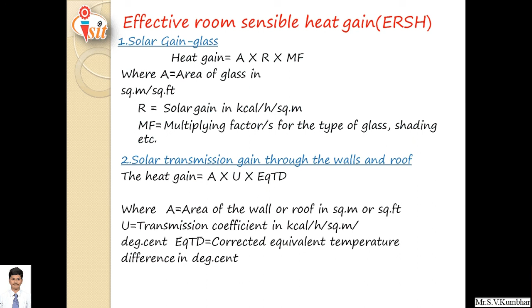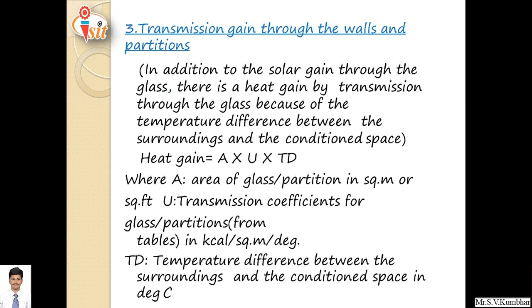Transmission gain through the wall and partition. Apart from solar gain through the glass, there is a heat gain by transmission through the glass because of the temperature difference between surrounding and conditioned space, and this heat gain is calculated by U into A into TD, where A is the area of glass or partition in square meter, U is the transmission coefficient for glass or partition, and TD is the temperature difference between surrounding and conditioned space.